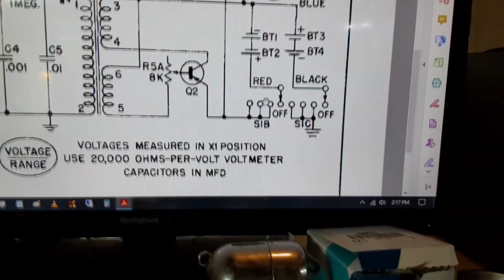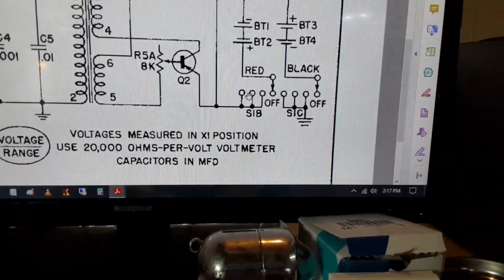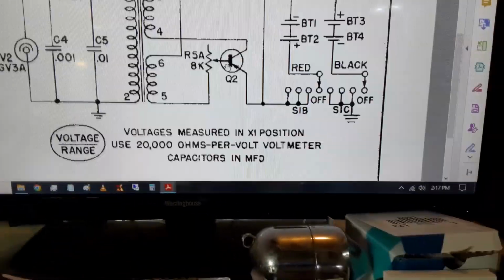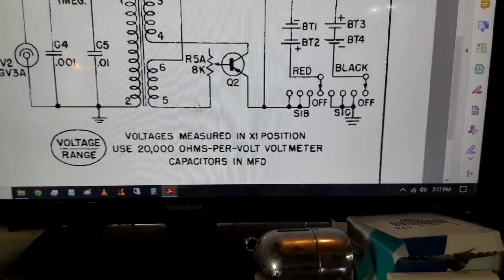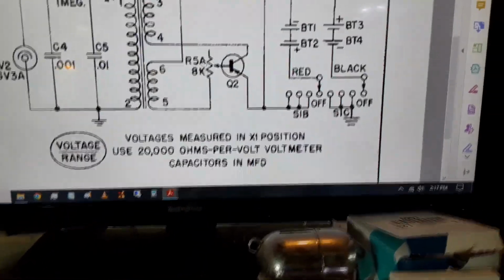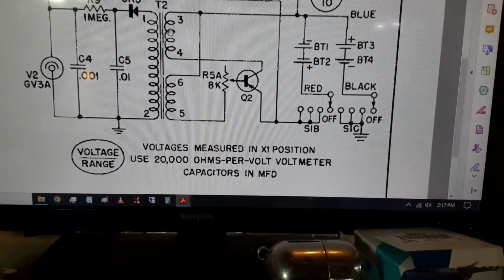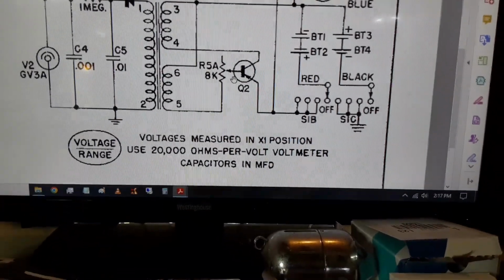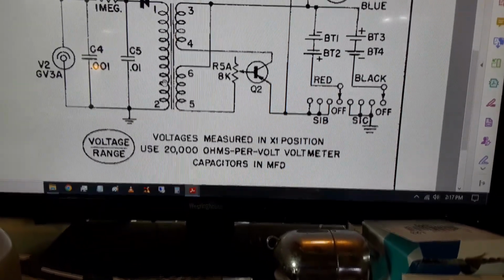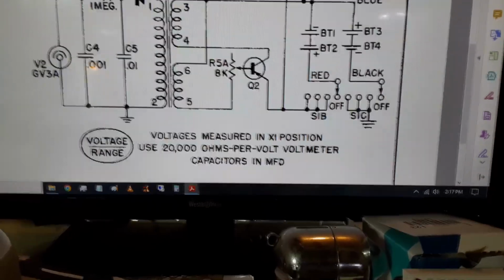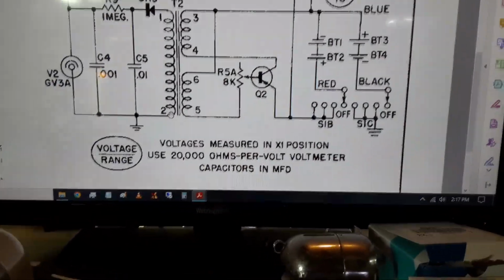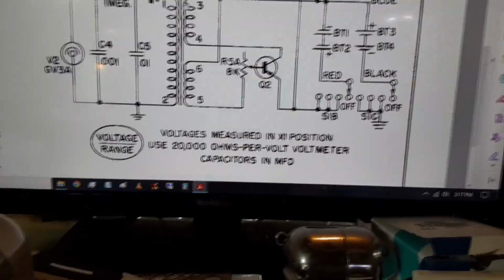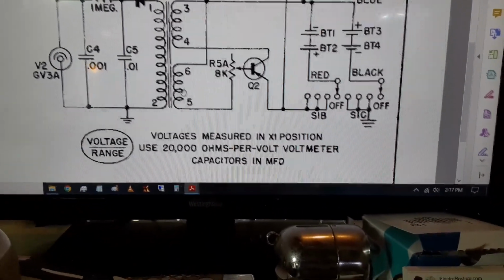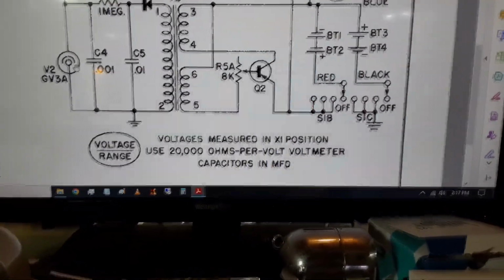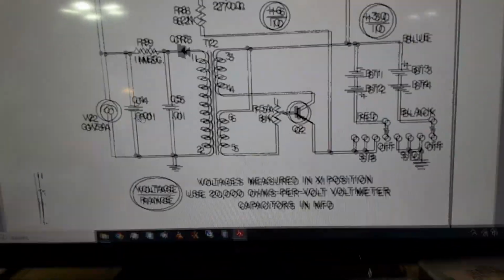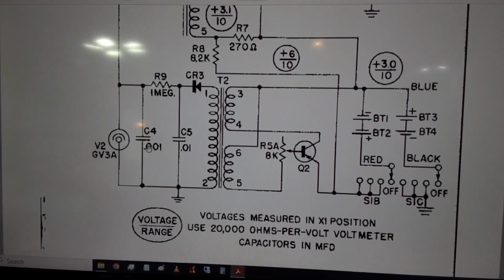Same thing here: times 1, times 10, times 100. All that does is, no matter where you set the switch, other than off, it's just connecting the battery to this Q2 transistor. And this is where the flyback action happens. This transistor oscillates, and when it oscillates, it sends a signal through here, and then it shuts off. And when it shuts off, the magnetic field here collapses and generates, these two magnetic fields collapse across this coil, which generates a spike of high voltage. And so this oscillates on, off, on, off, on, off, and that's what makes this pulse at high voltage, 900 volts or thereabouts. But we're not getting any high voltage.